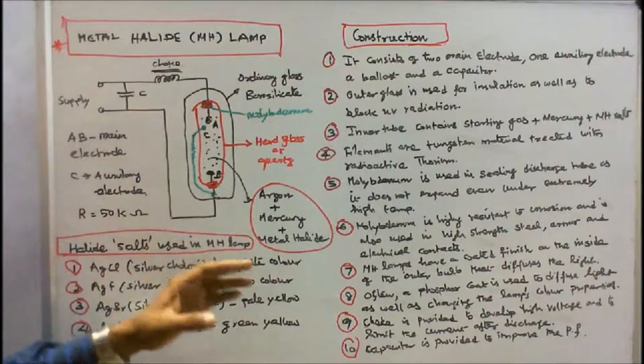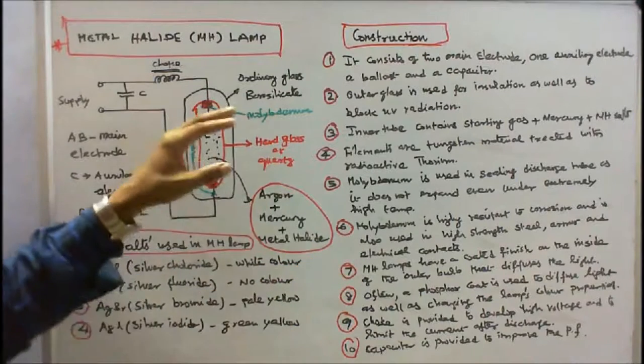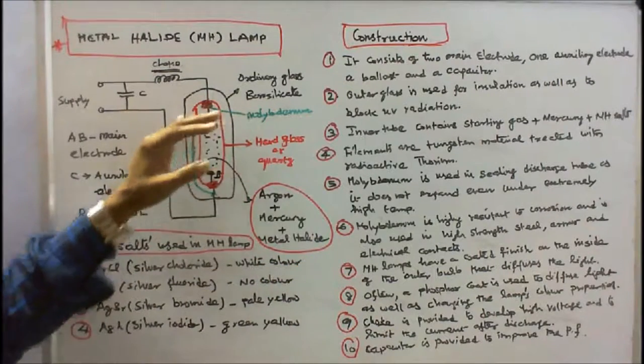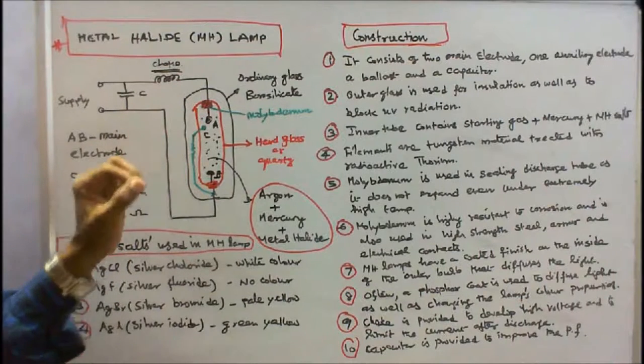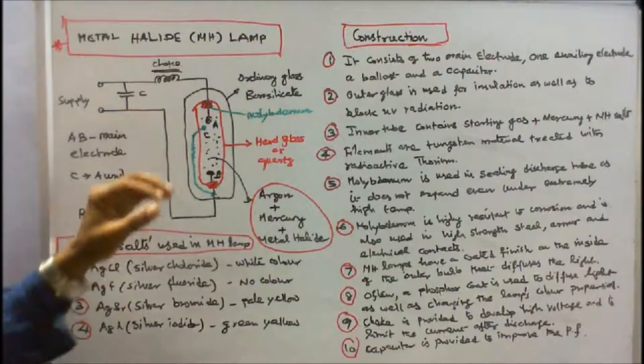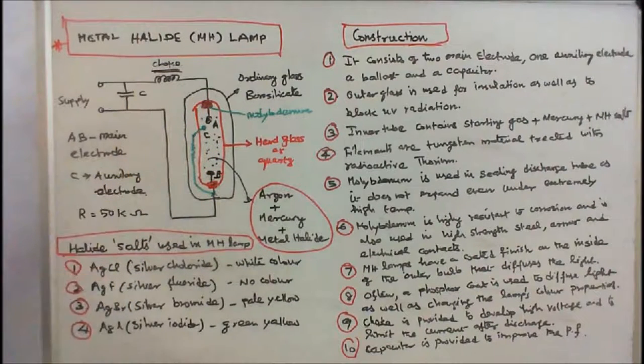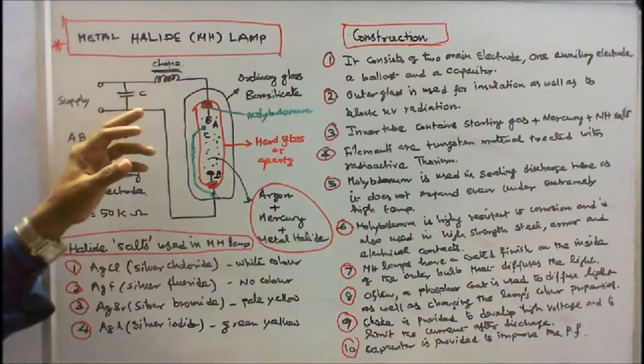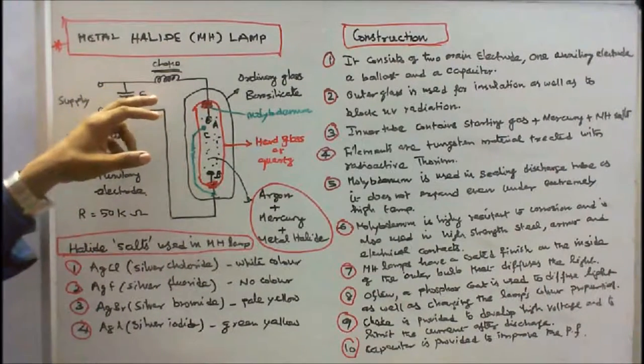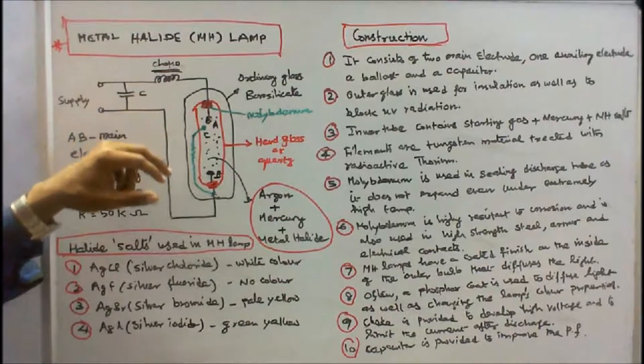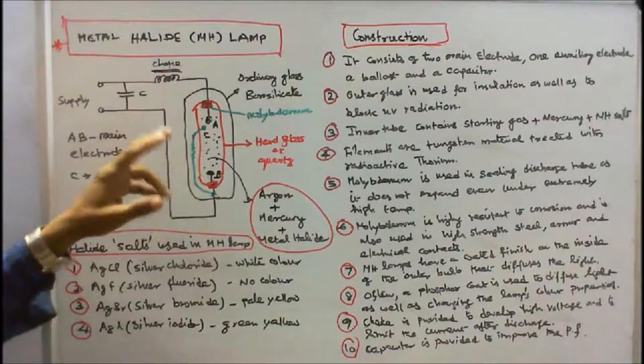Metal halide lamps have a coated finish on the inside of the outer bulb that diffuses light. Often a phosphor coat is used to diffuse light as well as changing the lamp's color properties. Choke is provided to develop high voltage and to limit the current after discharge. Capacitor is provided to improve the power factor.